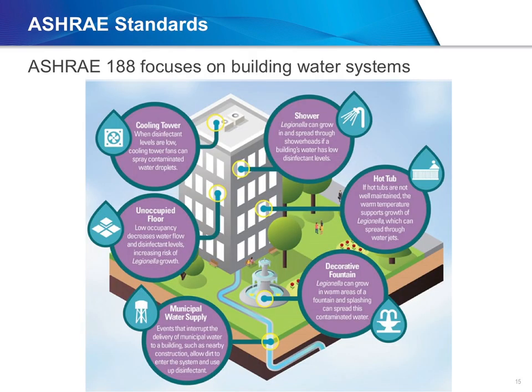ASHRAE 188 begins by pointing out that while Legionella bacteria occur naturally in freshwater environments, they become a health concern when they grow in building water systems that are not adequately maintained. It also recognizes that the mere presence of Legionella in a water system or device is not sufficient to cause disease. Rather, to cause illness, the bacteria must ultimately be inhaled or aspirated into the lungs of a susceptible person. Nonetheless, there are enough incidences of that happening to warrant a concerted effort to prevent Legionella growth in buildings.